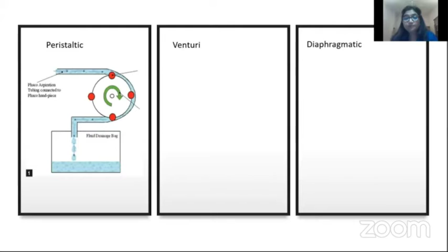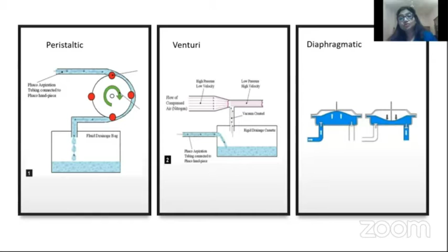Now, a venturi or a diaphragmatic pump does not wait for the vacuum to build up. And so sometimes it could be a little dangerous because it can pull not only the cortical matter or the nuclear fragments, it can also pull the PC. Now, in a peristaltic pump, more the flow rate, faster the pump will rotate.